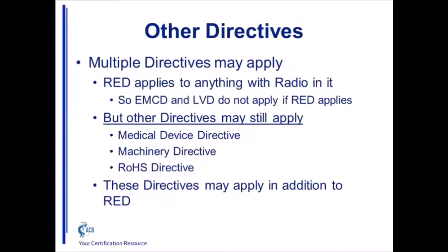However, the RED applies to anything with a radio in it, so now the EMC directive and low voltage directive do not apply if the RED applies, which means you do not issue a declaration to either of those other 2 directives because it's embedded in the RED.